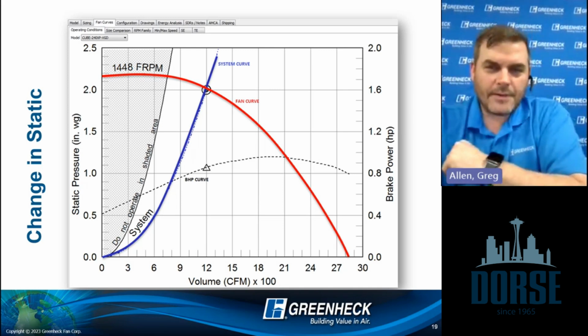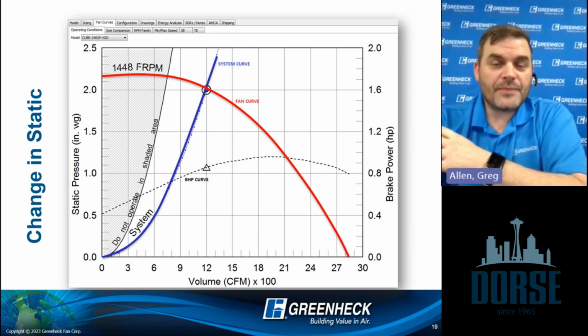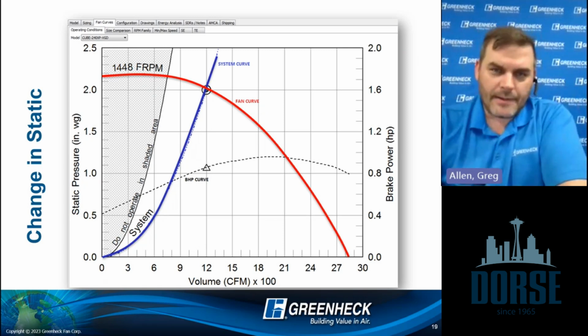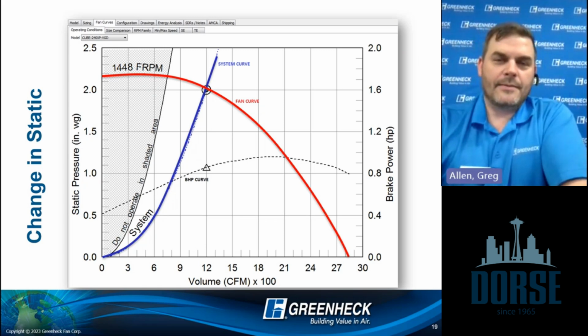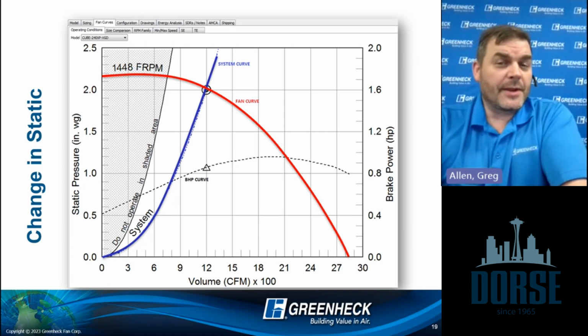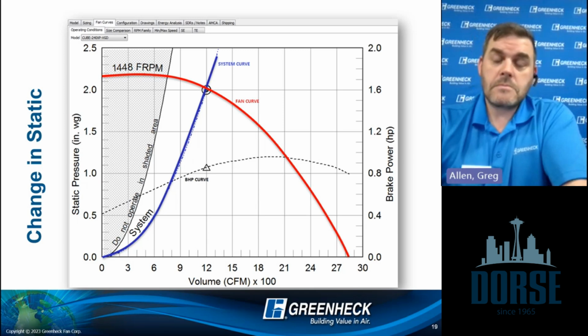And then it's installed. And you go back to do a review and your as-built, the ductwork is going around a couple of columns. That was not in your design, right? So what's going to happen? Static pressure is going to be a little different than you added because you didn't account for those extra elbows.